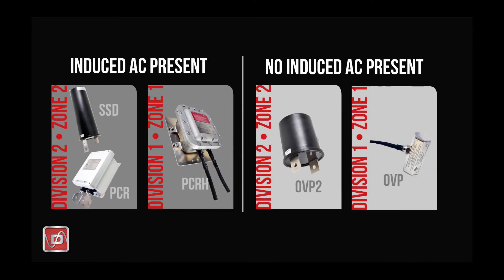This is due to the induced AC voltage forcing the device into switching into the full conduction mode, so think carefully about this topic. Now let's go back to our original chart and talk about hazardous locations. All electrical products rated for use in a hazardous environment are assigned some classification rating. All Dairyland products are rated for addressing flammable gases and vapors, designated by the industry as a Class 1 condition. Within this Class 1 designation, we further subdivide the rating into two different risks called divisions, or zones in other parts of the world. Products rated Division 2 or Zone 2 are suitable for use in those classified areas — implying that explosive gases and vapors are not normally present.